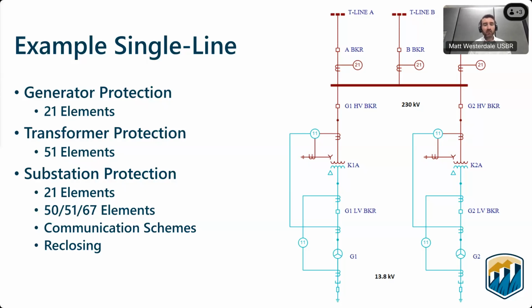In our transformer, we would have overcurrent elements on the high voltage side, which is the red winding in this picture. We have ground and phase overcurrent elements that are non-directional, also providing backup protection. These elements coordinate with our transmission owner's protection out in the substation.